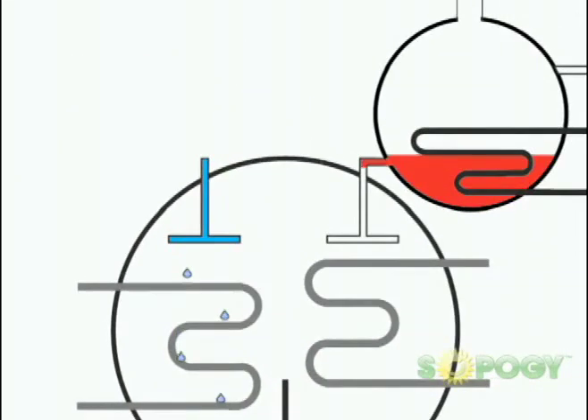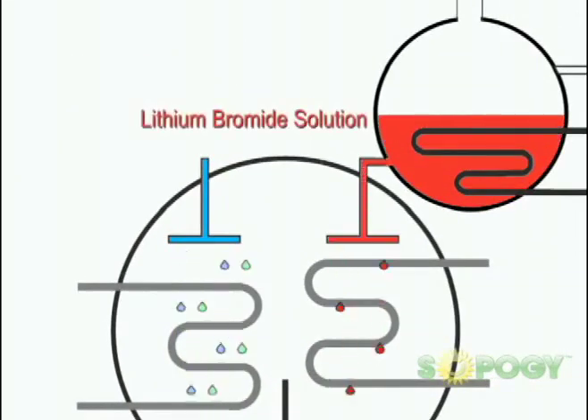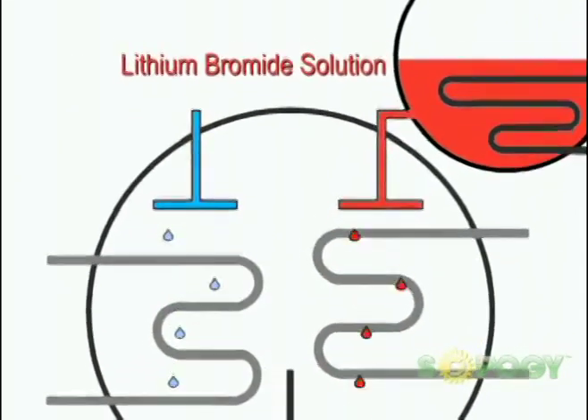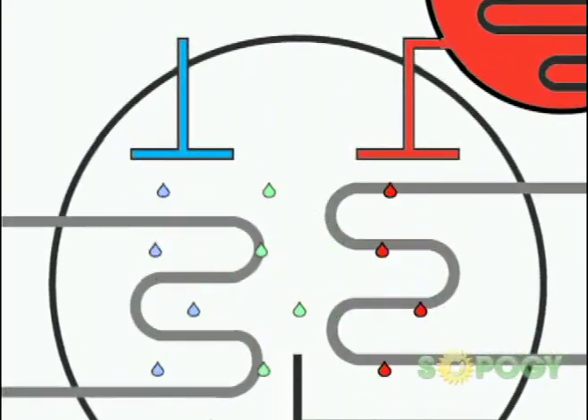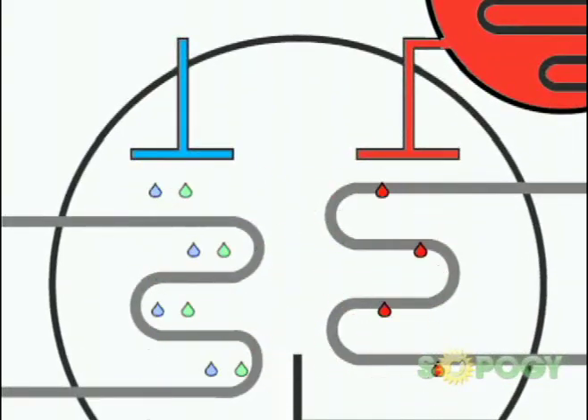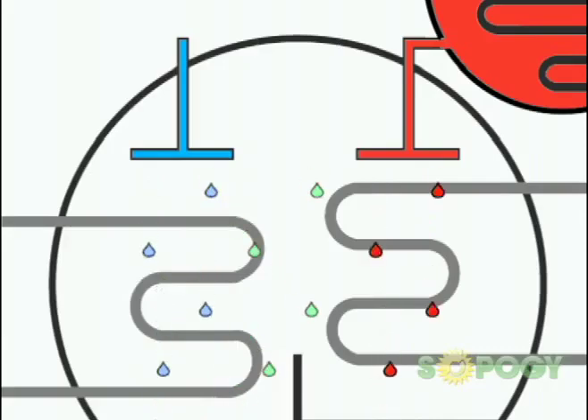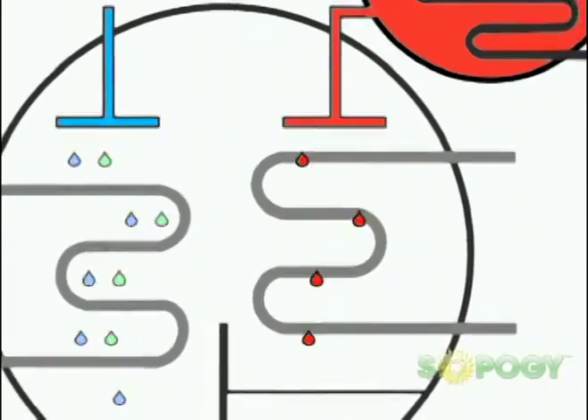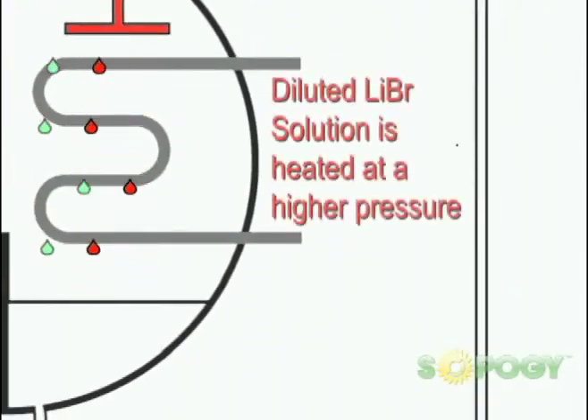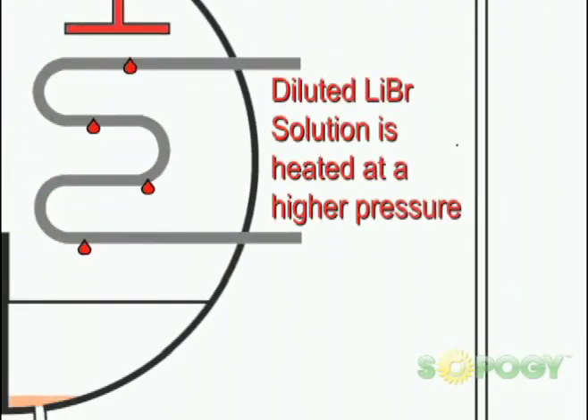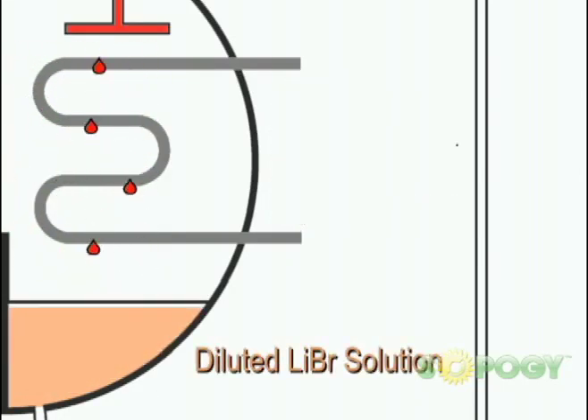Lithium bromide solution, which acts as the absorbent, is used to absorb the vaporized refrigerant. The evaporation of the refrigerant takes place at a low pressure. The diluted solution, which contains the absorbed refrigerant vapor, is heated at a higher pressure. As lithium bromide becomes dilute, it loses its capacity to absorb water vapor.